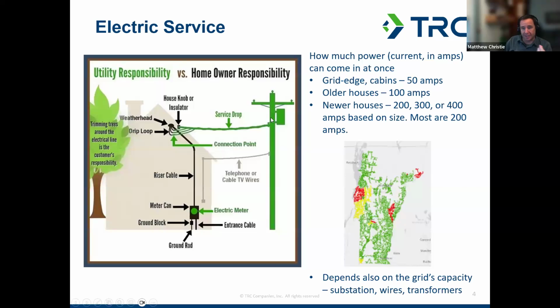What's really limiting your power is the amount of electricity that can flow across this service drop wire. This is a single point of entry, which is paired with the amount of power your meter can pull in and distribute. For most houses those two items match, but for some houses there's a mismatch, and in that case whichever is lower is the fundamental limiting factor.